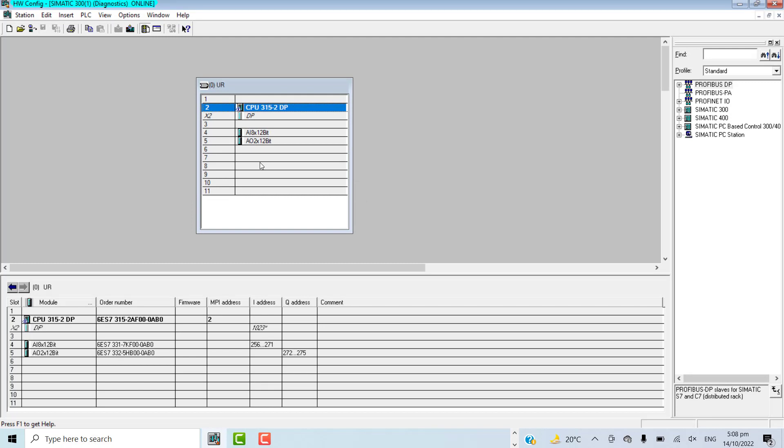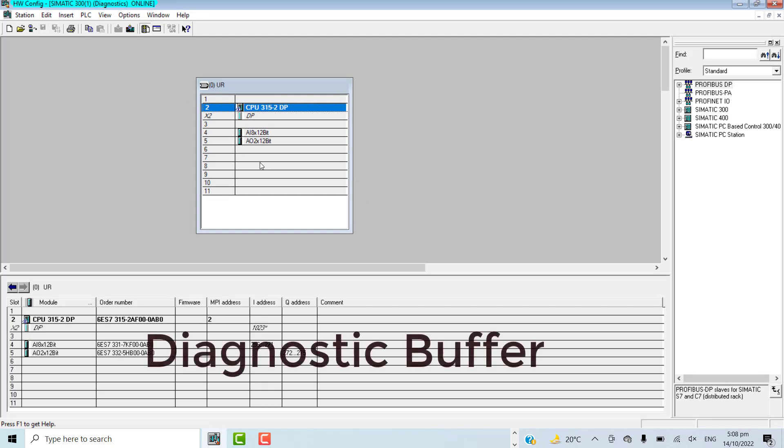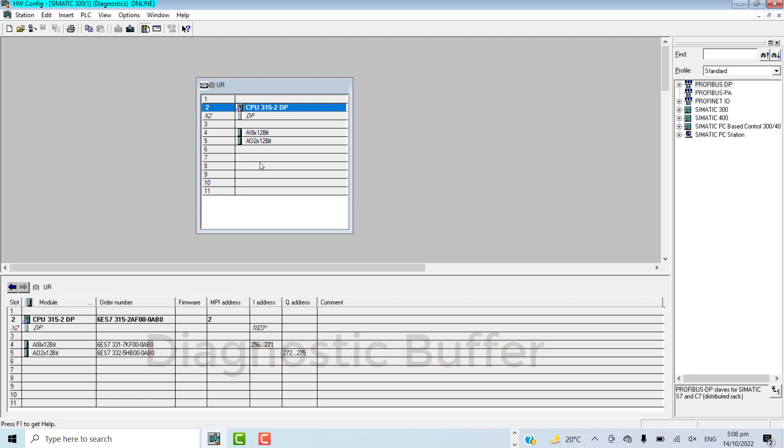First of all, I will try to save the diagnostic buffer. The diagnostic buffer is the collection of events. For example, if we stop the PLC, memory reset the PLC, or switch the mode from stop to run mode, all these events will be saved into the diagnostic buffer.